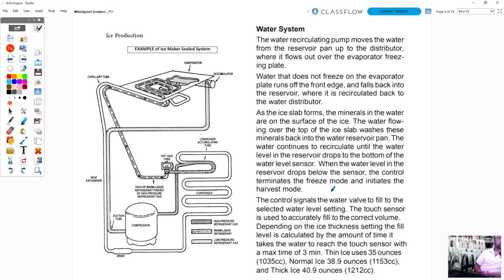So if we look here in ice production, we're going to go through how refrigerant flows through the system first. So the compressor pumps out through here, what we call the discharge line. This is where the condenser accumulating tube is. I think that's just this big fat tube that you'll see right in front of the condenser when you open up the front of the unit. And you'll see a pipe going to the condenser or going to the hot gas valve. So if you are cooling and creating ice, the refrigerant's going to flow here into the condenser first. This valve will be closed, so the Freon can't go that way. Go through our condenser this way, through the filter, and up through our capillary tube into the evaporator here.